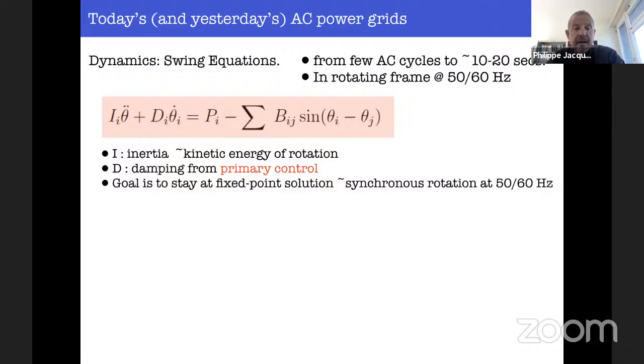And then on the right-hand side, you have a balance between injected power, the PI for instance, or collected power, and the power that flows through the grid away from node number I. When this difference is 0, that means there is as much power going in as going out. The angle, the frequency, doesn't change. The derivative of the angle is 0, the second derivative of the angle is 0, and I'm back to the original power flow equations.